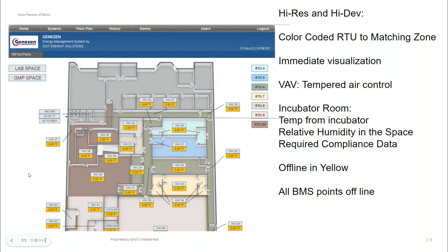In this example, again, additional data is required to be in compliance. VAV4 in the center of your screen would typically just have a temperature being monitored by the BMS. In this case, from the CloudLink we're seeing temperature, humidity, pressure, and door status. Those are all wirelessly fed into the Sonicu solution, but then we've mapped those back via CloudLink into the BMS so they can visualize that, no different than you would have in a typical BMS environment.